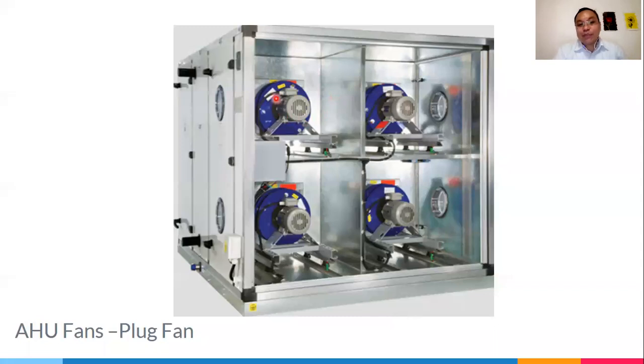Another good thing about the plug fan is you can use smaller fans. In a centrifugal fan, you're limited to just one unit. But with a plug fan, since there's no housing, you can use smaller fans and multiple fans at the same time, provided your electrical engineer is very good at calculating the electrical loads of the fans.